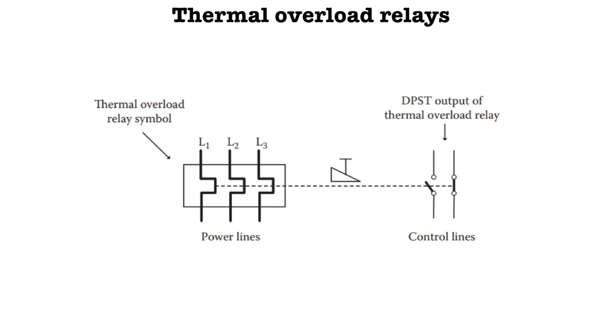The relay typically features double pole single throw (DPST) contacts that switch states in response to the bimetallic strip's bending. This contact can either stop the motor or provide an indication of an overload condition. The strip can be directly heated by the motor's current or indirectly through an insulated winding. During normal operation, the strip remains straight, and the relay contacts maintain their default positions.